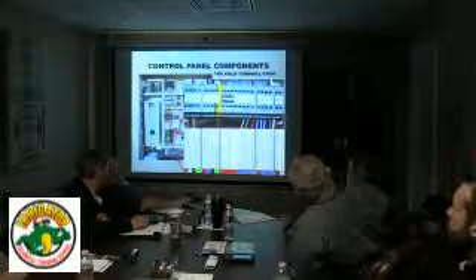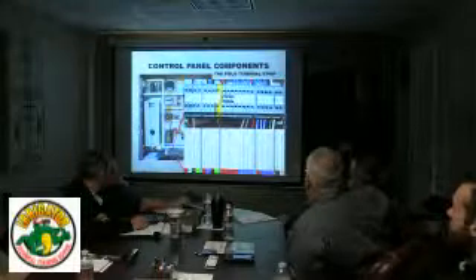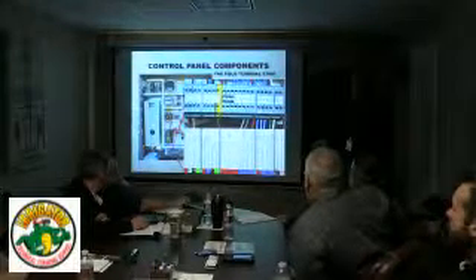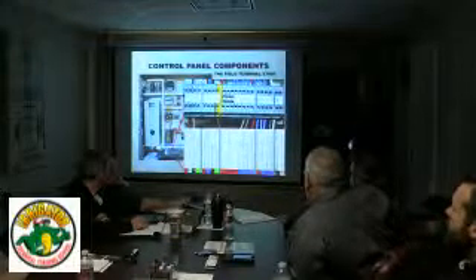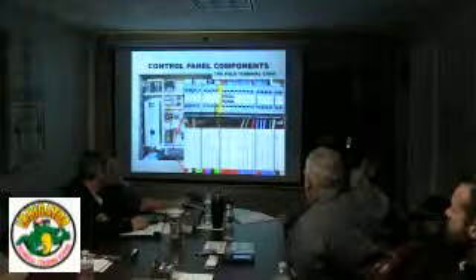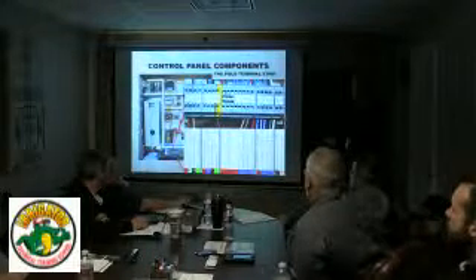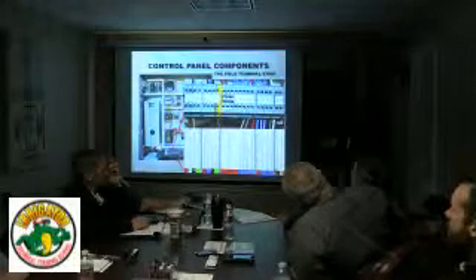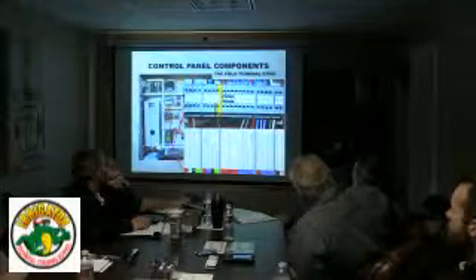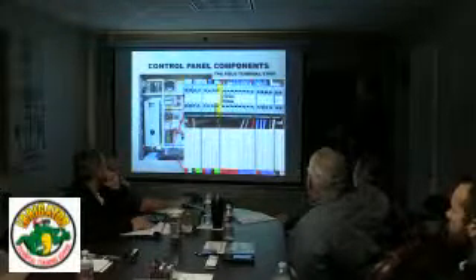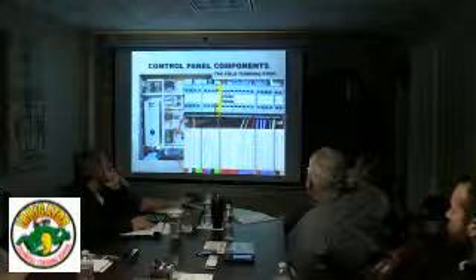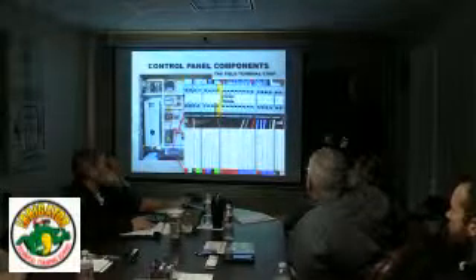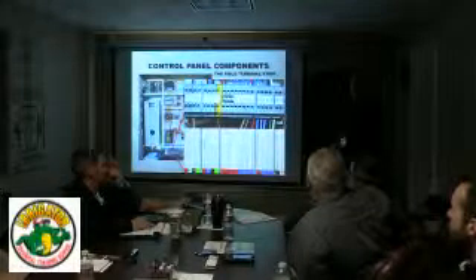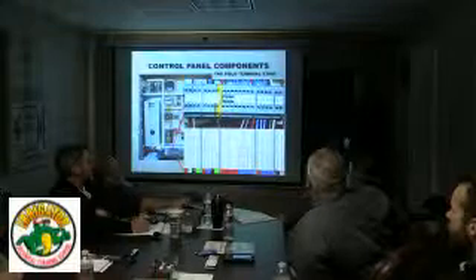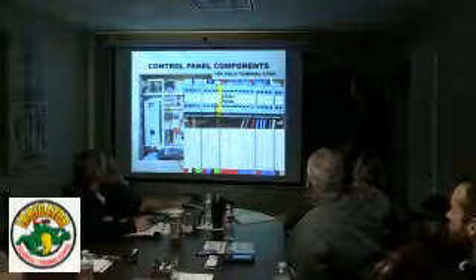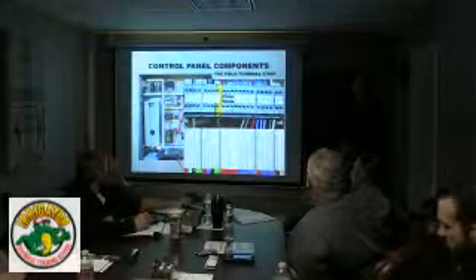Again, I'll point out the field terminal strip. Here's an example of a sticker, a label that you'll see right below it, down in the bottom of the panel. It corresponds to every one of these that's numbered. Like I say, you can test the pressure transducer right here, check a flow meter. The remote start input that we were talking about, if it has that local remote switch, that would be an input. Temperature switches, flow switches, they're all right here. So you can simply start pulling these wires out if you're testing, like I said before, the power supply, or you may have to pull one out and put a meter on it and test it. So keep in mind the field terminal strip, what it is, and it can be useful too.